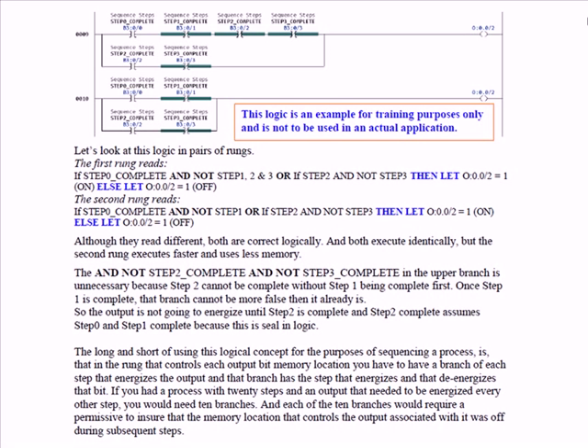So if you compare those two rungs, they both behave exactly the same logically. If step 1 is not complete, then only step 0 could be complete. So once step 1 is complete, we don't need not step 2, not step 3, because they're sequential. So both those rungs are identical.